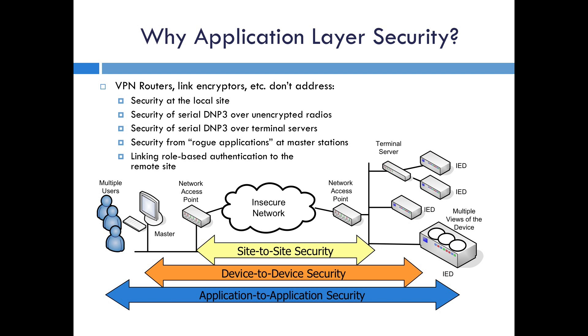Finally, there's application-to-application security, which ensures that individual users — not just devices — are authenticated by the remote devices, and that the authentication information will be carried wherever the message travels. It permits remote outstations to perform role-based authentication and authorization, so that the level of security required changes depending on who is attempting to perform an operation.